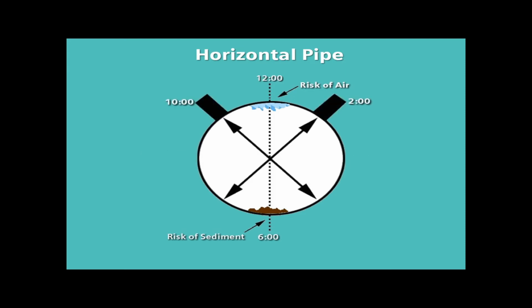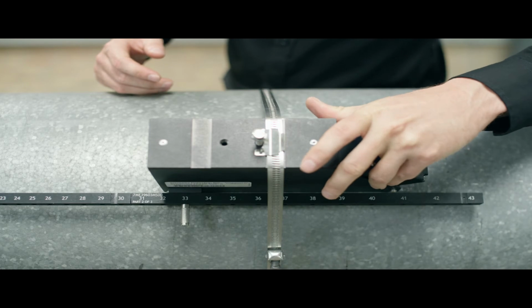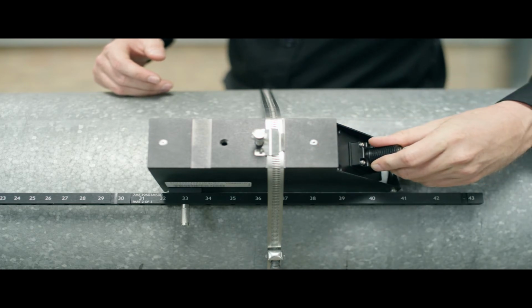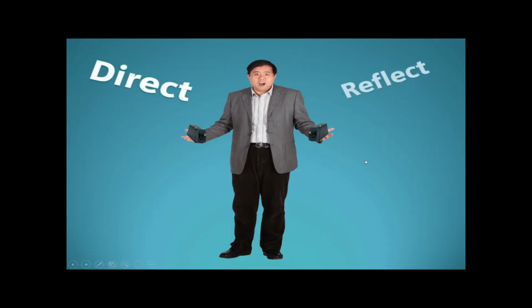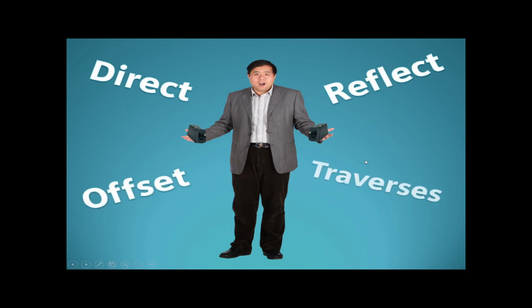If you're installing a dual path system, we generally recommend using the 10 o'clock and 2 o'clock positions. This locates the flow sensors 90 degrees apart, which will provide the best averaging since it cuts the pipe into 4 equal parts. So that brings us to actually installing the sensors. When should you choose direct or reflect? What is the spacing offset? And what is a traverse?